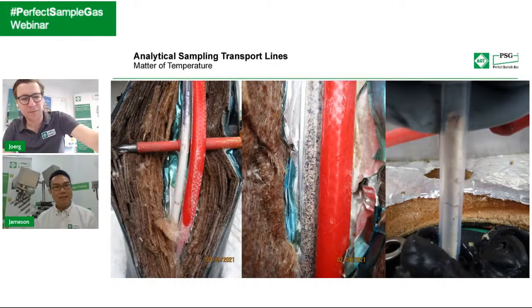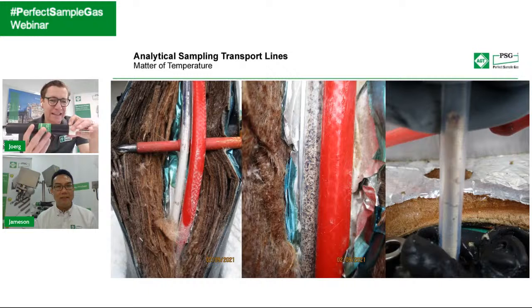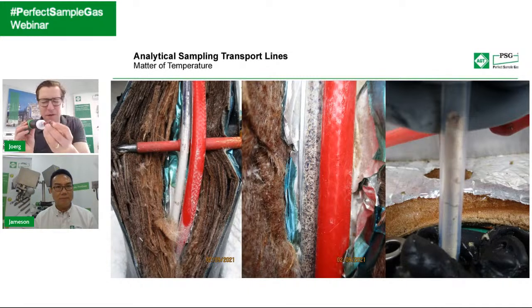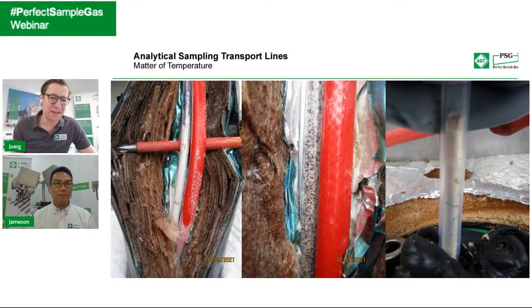So inside the components of a heated sample line, and this is sometimes maybe a little bit underestimated, the heated sample line represents the longest surface of all components in the sample handling system. So if you choose some bad material, or if this material, for example, shows some outgassing or some other effects, this will also affect your probe. Therefore, I think it's quite important to choose high quality products and to make sure that your line is heated everywhere. Sometimes when you have a zone heater and you cut this at the wrong place, you will see some problems there because there might be a cold spot even in the line. Absolutely, yeah.